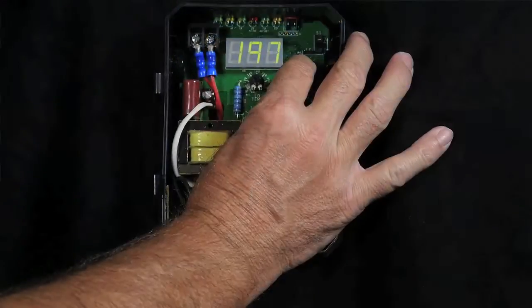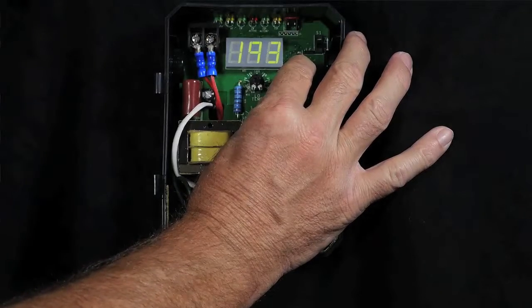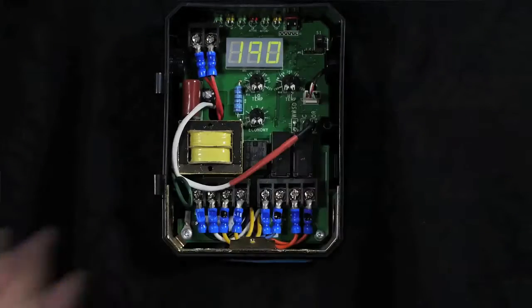The lowest target temperature calculated by the hydrostat is 145 degrees. The highest temperature is the high limit set point, which you determine. When speaking about thermal targeting, I like to make the analogy to cruise control on a car. You set the speed limit, and the cruise control determines how much engine power is needed to maintain that speed.